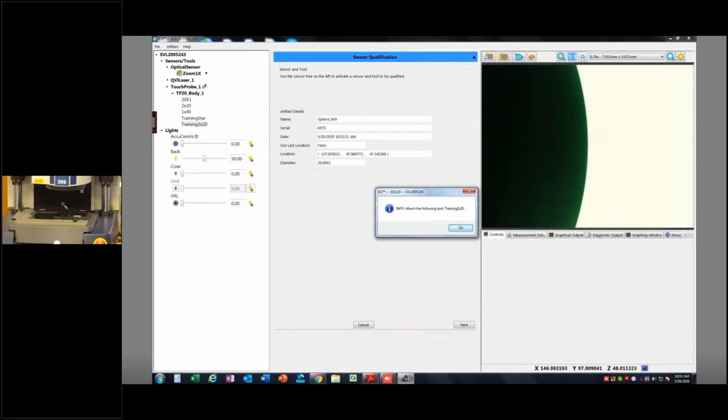If you've never used these probes before, right on the body here, there is a series of symbols. There's a triangle, a half circle, and a half, I guess it's a half a diamond, half a circle, and a half of a rectangle. And then the other half would be on the module, and you can just kind of marry those up. It does just kind of clock on there one way. So if it's not sitting nice and firm, then you probably don't have it on there correctly, but make sure you got it on there nice. You can kind of give it a little twist, and it shouldn't twist on you. Okay, so now it's on there. I can hit OK.